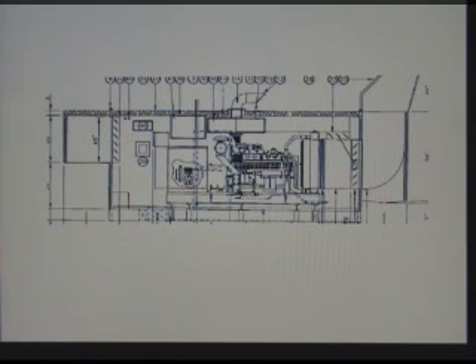And so this is an enclosure we used on the CNRL project. The airflow is inwards and upwards across a set of dampers, which are designed to maintain a reasonable temperature inside the enclosure. Across the engine, cooling the engine, across a big radiator, and then out a discharge duct which has noise attenuation and takes the hotter air and just ducts it straight upwards into the atmosphere. The engine sits here, the exhaust is up through a silencer and then through the roof and out, and then the generator sits here. On the CNRL job, we asked that the genset power terminal box be mounted up high and on the side so that we can just come in through the side of the enclosure to pick up the cables rather than trying to stub up through the bottom.